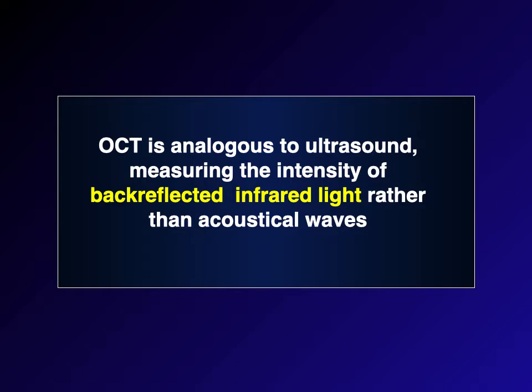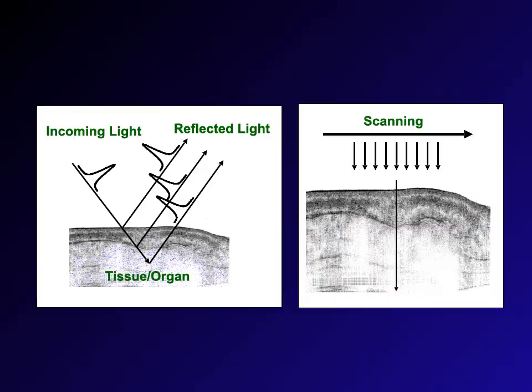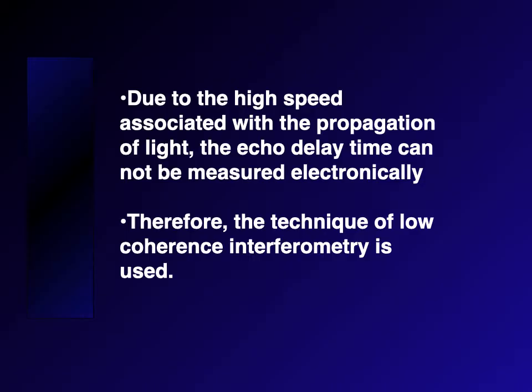The next slides are ones we used in the 1990s because we don't do many of these basic talks anymore. OCT is analogous to ultrasound, measuring the intensity of back-reflected infrared light rather than acoustical waves. Low-coherent infrared light pulses are generated at the sample. The time for light to be reflected back gives you distances, and the intensity of back-reflection is plotted as a function of depth, analogous to ultrasound. It's called LCI in one dimension, and in two dimensions it developed the name optical coherence tomography.